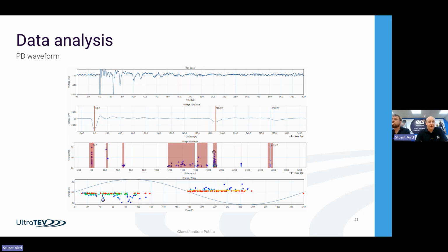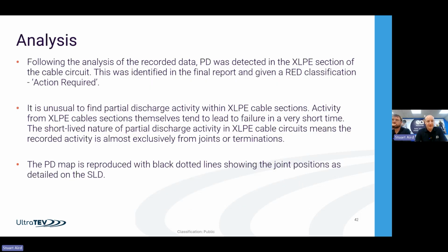So the technique for doing it is you mark your initial pulse, location pulse, and the end one. With this, generally you get more locations because you've got varying voltages, so you can pick up some at lower voltage and then some might come in at a higher voltage. So we can plot all those along the cable, and at the end of the testing you will end up with a map of the cable circuit that we can then do the analysis on. Following the analysis of the data, we put in locations of the joints that have been provided by the customer, and we could produce a map of that cable.